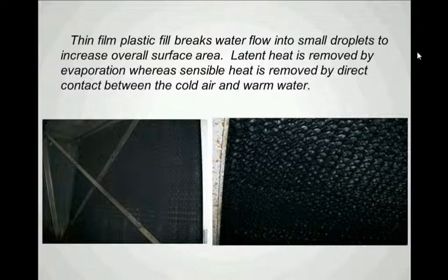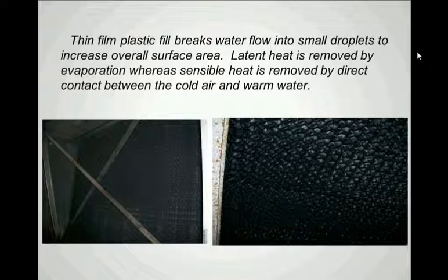In this case, latent heat is removed by evaporation, whereas sensible heat is removed by direct contact between the cold air and the warm water. So in colder areas of the country, that cold air has a big impact on the performance of the cooling tower, and not all of the cooling has to take place by evaporation.